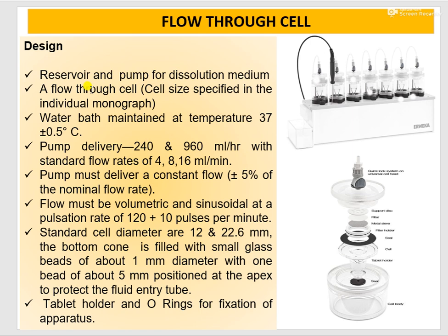There will be a flow through cell. Cell size will be specified in individual monograph. So we can have large flow through cell, we can have small flow through cell. Both types are available. So depending upon what is mentioned in monograph, you have to use that size cell for particular dissolution study. Again, there will be a water bath maintained at temperature 37 plus or minus 0.5 degree centigrade.